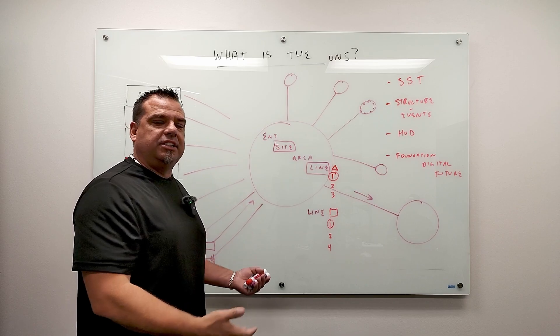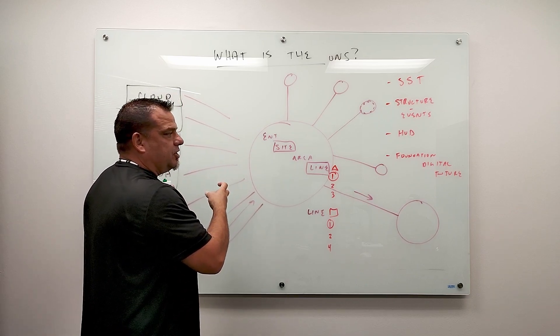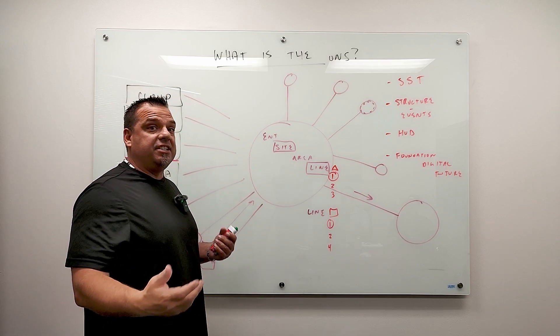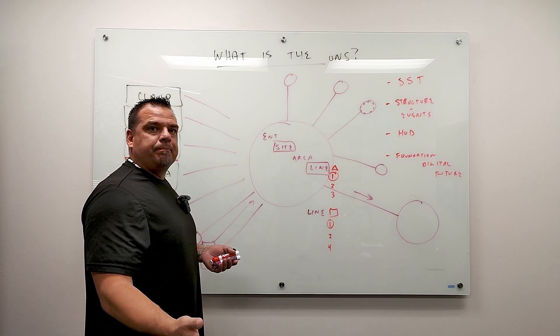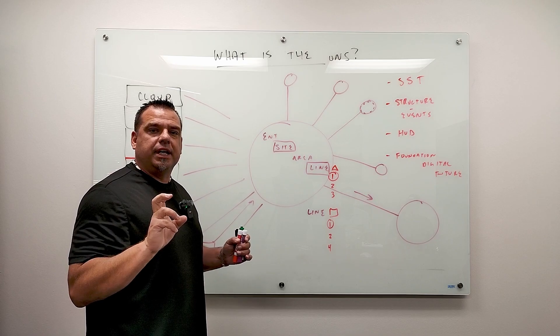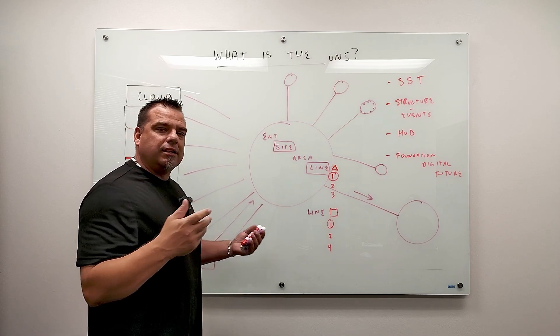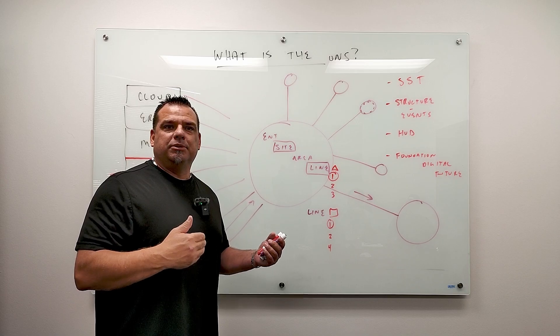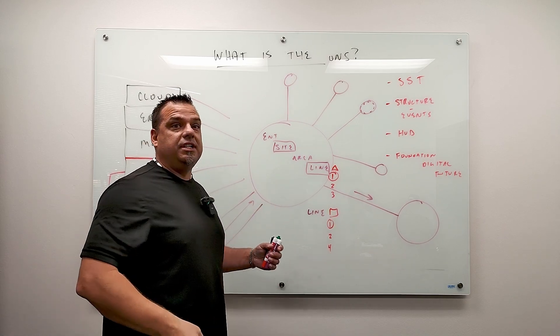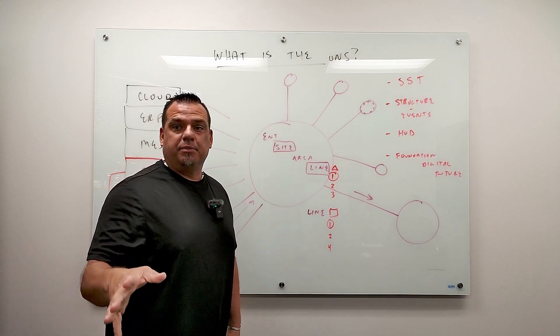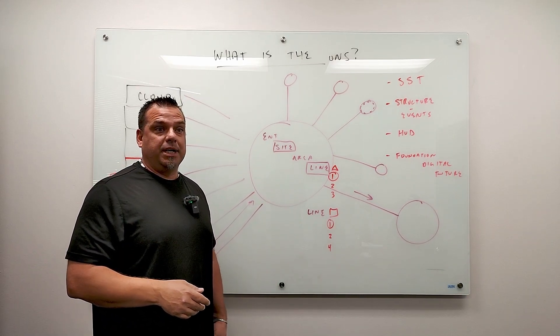Okay. That's the open architecture piece. This is, that's the technology centric piece. We built the infrastructure on a common protocol that has a standard called Sparkplug B, which is open managed by the eclipse foundation. But the softwares we are using are irrelevant. They only have to meet our minimum technical requirements, which are in our case, you have to support MQTT. You got to scale to this level and you got to support the MQTT Sparkplug B standard managed by eclipse.